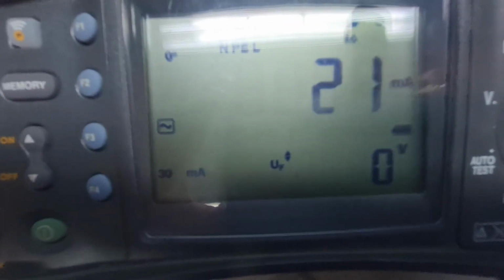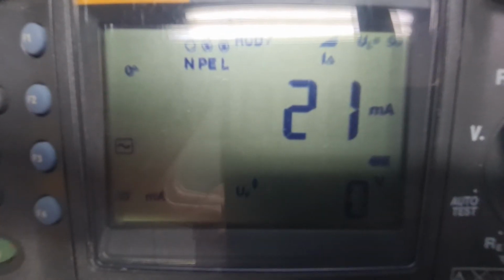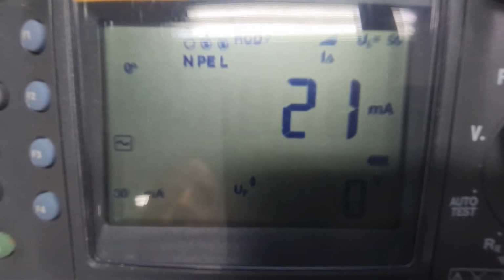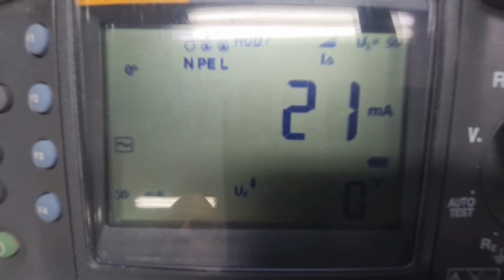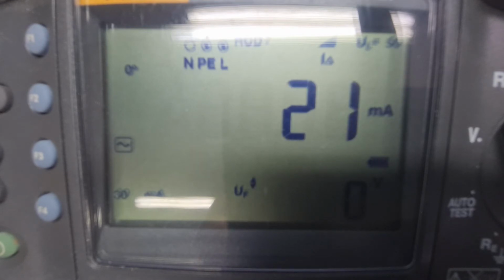So we have our instrument which is set up. Currently it is set up at 30 milliamps type AC. I will press the test button. I have to energize the system, so I am arming the RCD. Okay, we can see that we have the lightning symbol. It means that there is power detected across the instrument terminals. I press test and see what happens, and we get a tripping time of 21 milliseconds, which is a reasonable value for the RCD, and we also get an RCD pass.